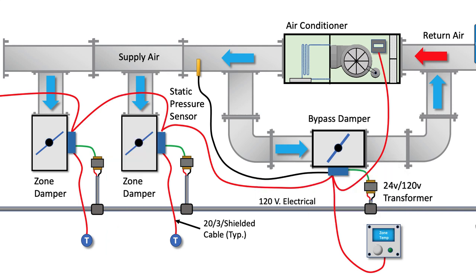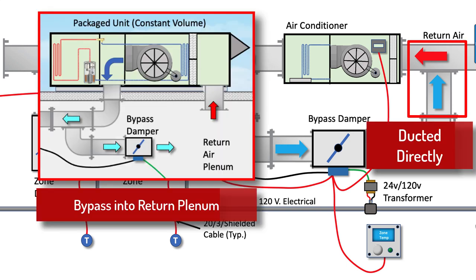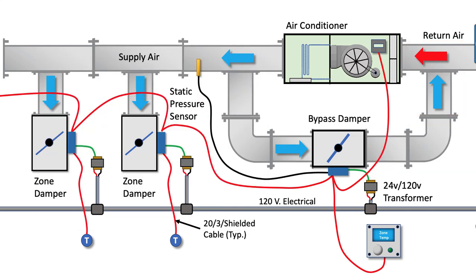There are two simple setups for the bypass air: it can either be ducted directly into the return air duct, or it can be bypassed into the return air plenum if the plenum is rated and approved for this use. Because the fan is always running at constant speed, there is no fan energy savings when zone dampers start closing, as opposed to a true VAV system where the fan speed is reduced.